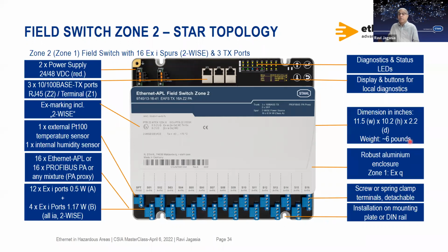Some buttons and displays for diagnostics. Dimensions approximately 6 pounds. It's a robust aluminum enclosure. The zone 1 certification is achieved with Ex q protection method. Screw and spring clamp, as I mentioned earlier, for the Div1 solutions or for the SPUR solutions. And then you can install this on a DIN rail or on a back rail.